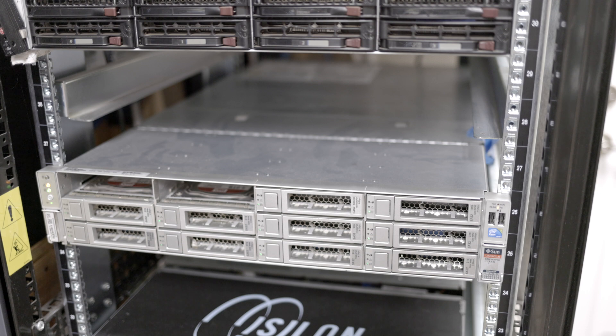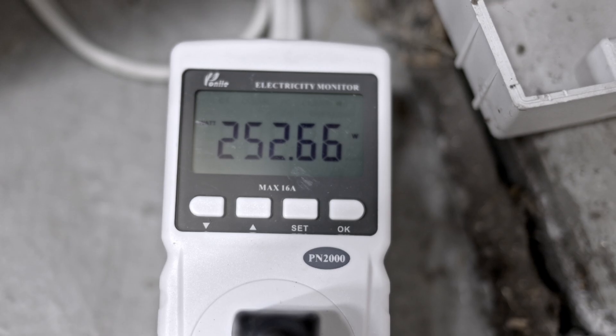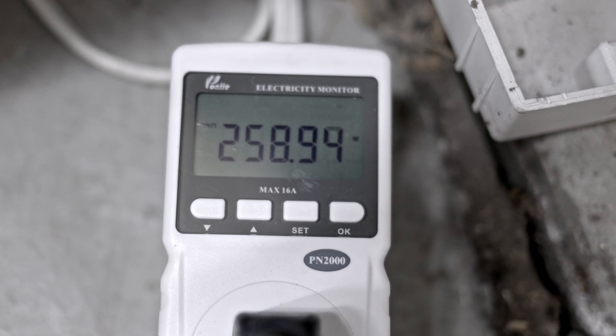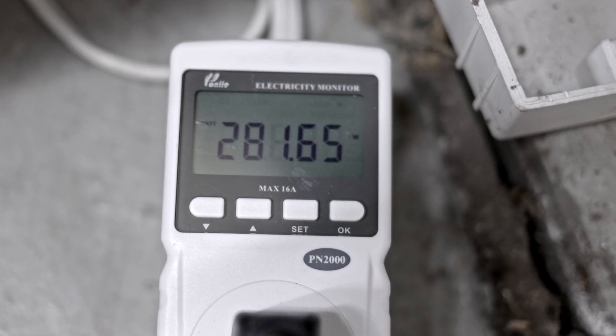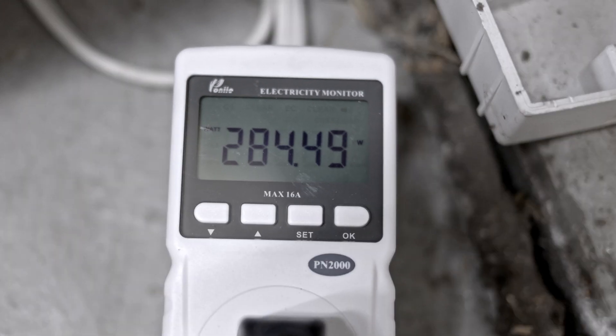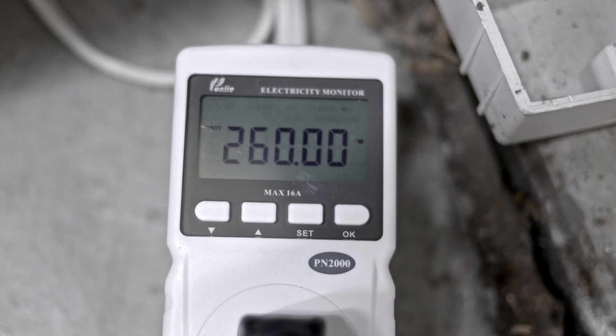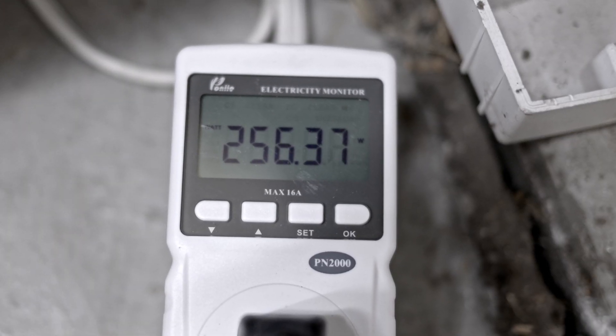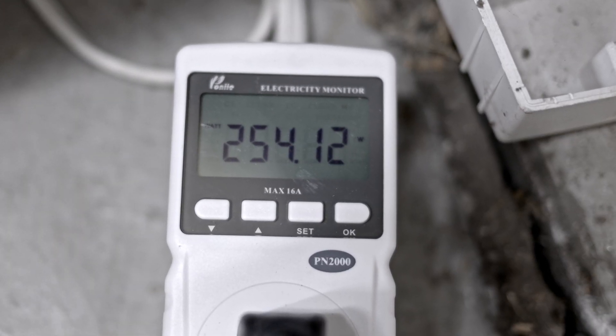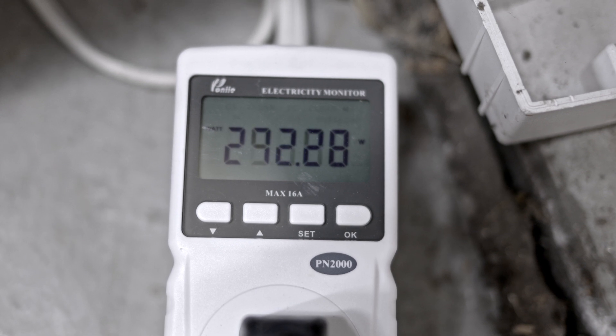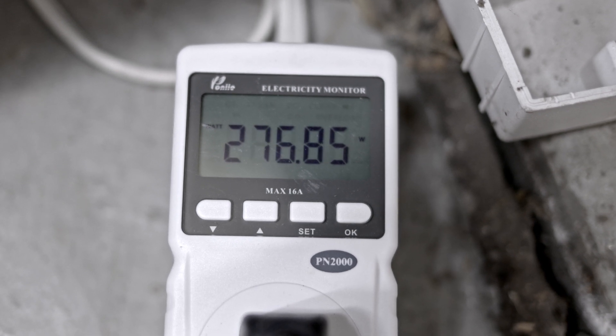This also likely is saving a lot of power because each one of these fans is rated for up to about 25 watts. The server is now running with my relatively normal load and the power is going from about 250 to about 280 watts.